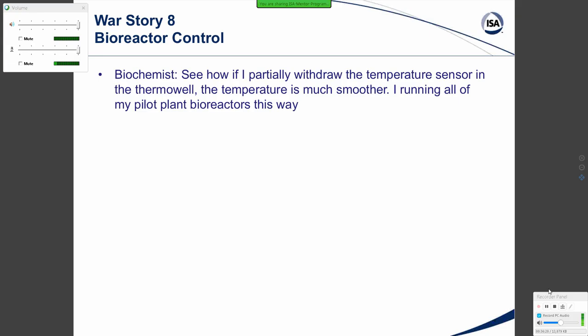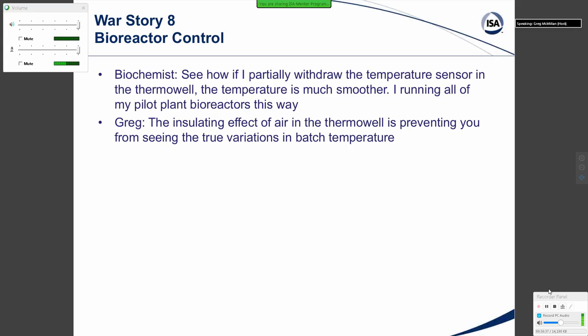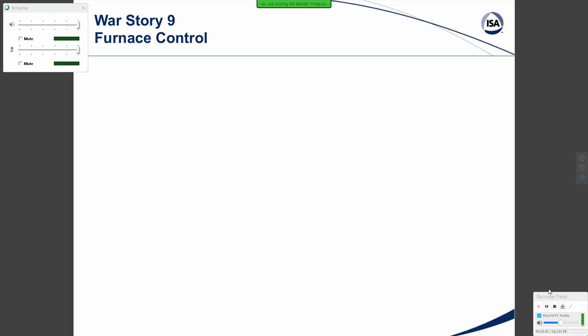War Story Eight: Bioreactor control. A researcher showed how partially withdrawing the temperature sensor in the thermowell made the temperature reading much smoother, and said he was running all of his pilot plant reactors this way. The insulating effect of air in the thermowell was preventing him from seeing the true variations in batch temperature.